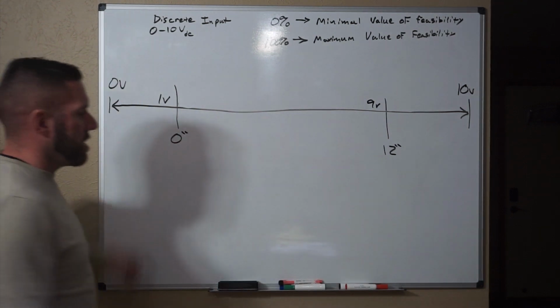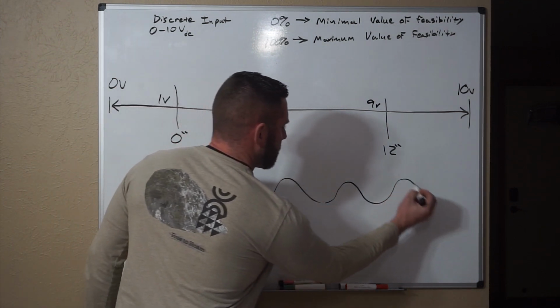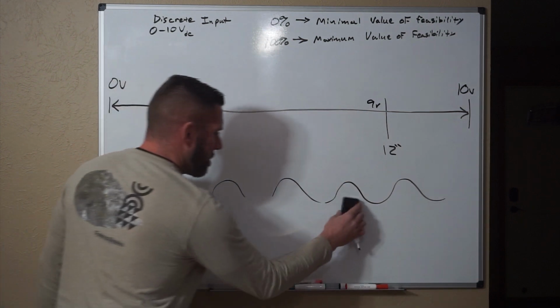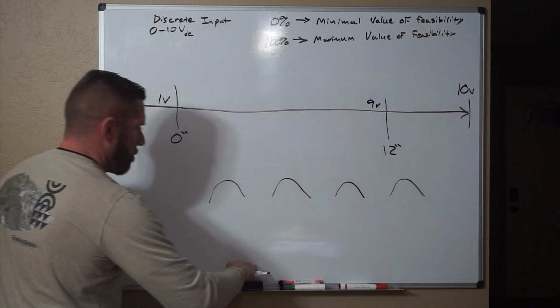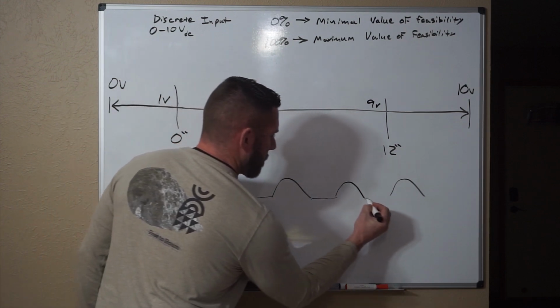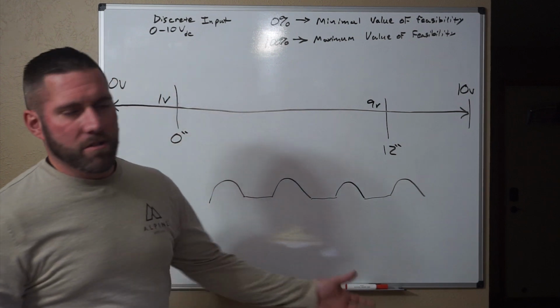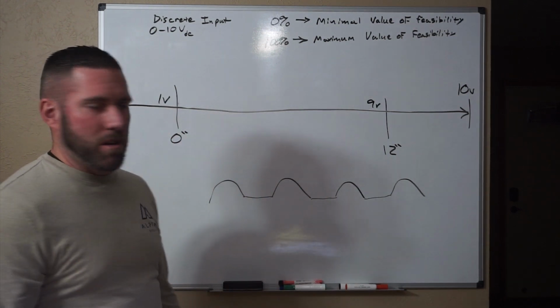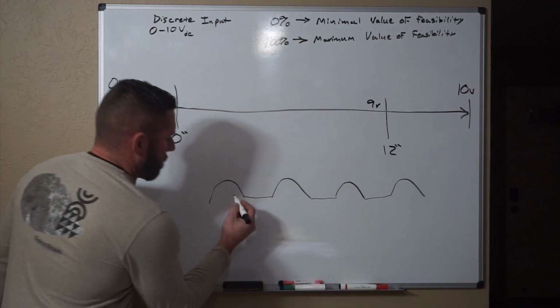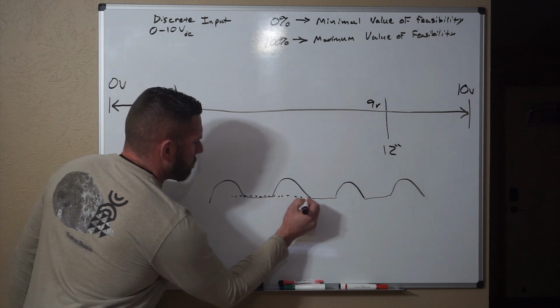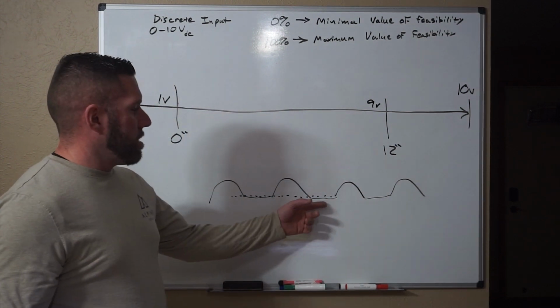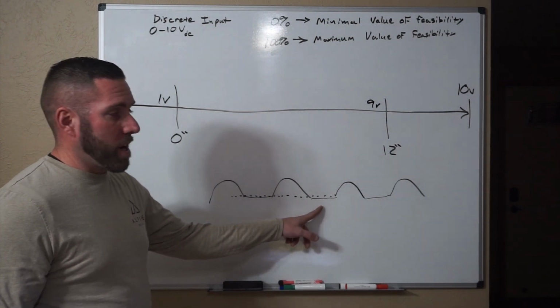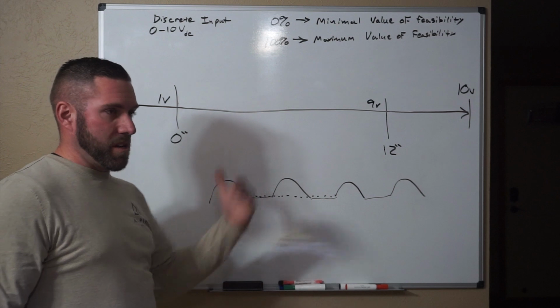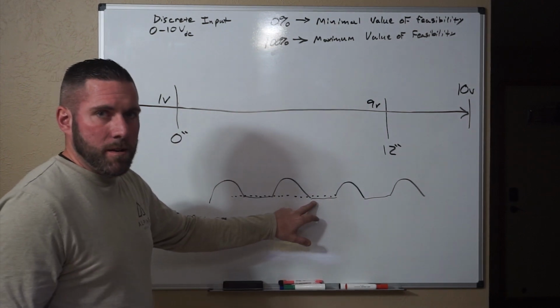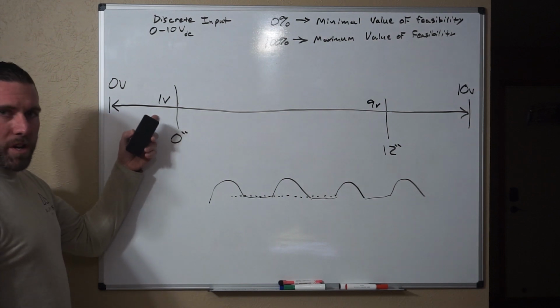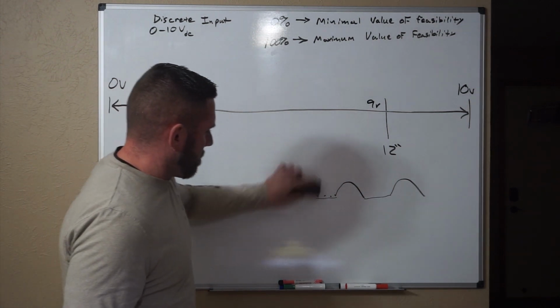We do not want to have something down here going like this on a graph, and the only thing we can see is this. We do not want something to show up in what they call harmonic distortion, clipping, total distortion, whatever you want to call it. That's not okay, because our alarm line might run all the way across here. What you're doing is you're about to be above the alarm, so the low alarm or the high alarm, depending on what the sensor outputs, if it's 10 to 0 or 0 to 10, you would never see it. So to be sure, you put it inside of the range of the sensor.